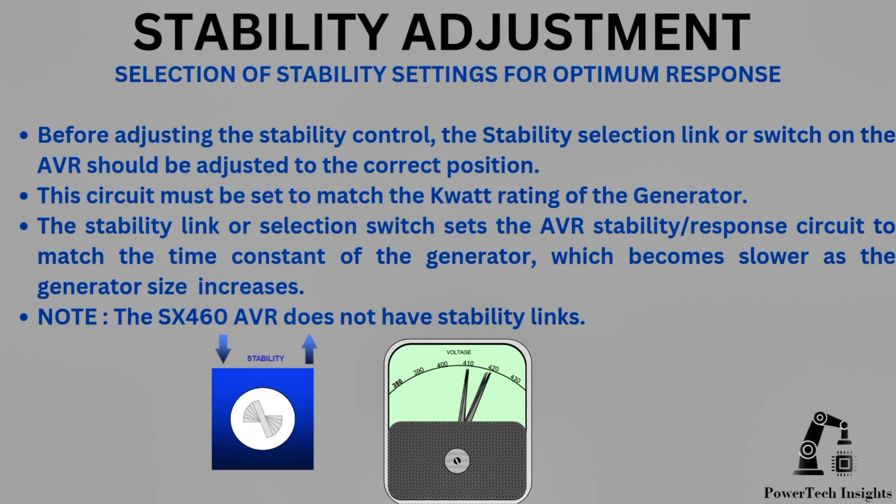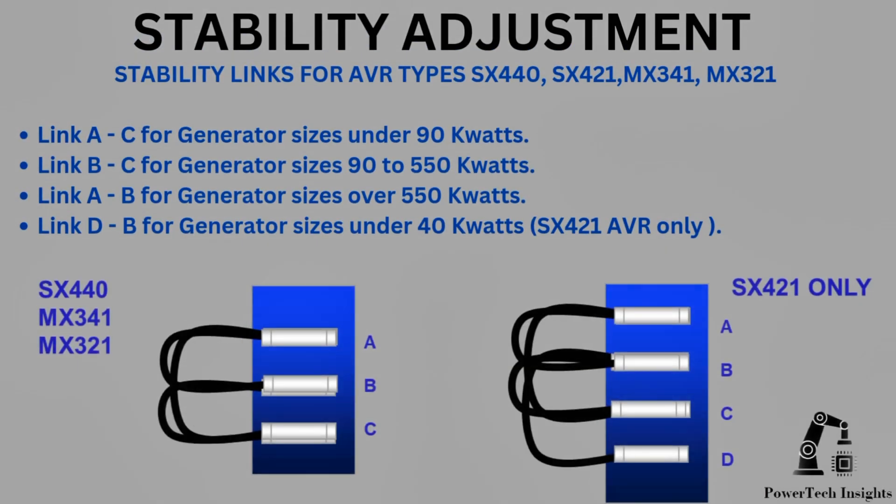Stability Adjustment. Before adjusting the stability control, the stability selection link or switch on the AVR should be adjusted to the correct position. This circuit must be set to match the kilowatt rating of the generator, as the stability link sets the AVR stability response circuit to match the time constant of the generator, which becomes slower as the generator size increases. Note: the SX460 AVR does not have stability links. For AVR types SX440, SX421, MX341, and MX321: link A to C for generator sizes under 90 kW; link B to C for 90 to 550 kW; and link A to B for over 550 kW.